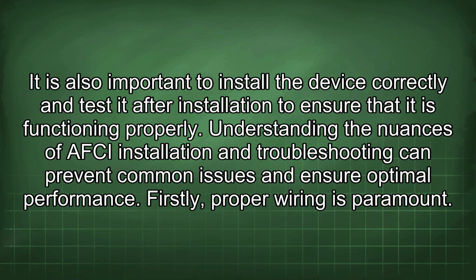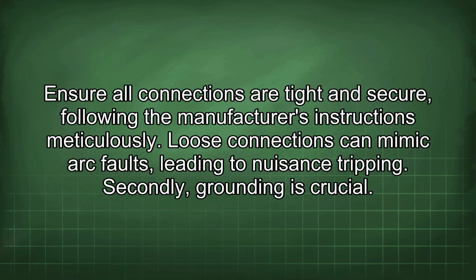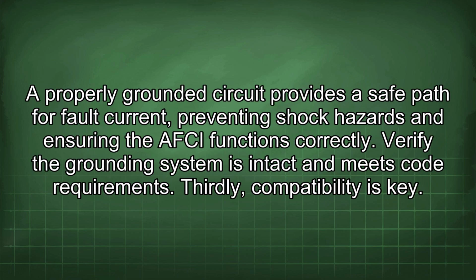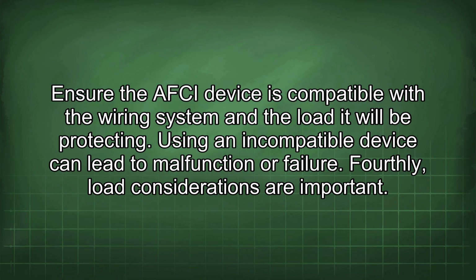Firstly, proper wiring is paramount. Ensure all connections are tight and secure, following the manufacturer's instructions meticulously. Loose connections can mimic arc faults, leading to nuisance tripping. Secondly, grounding is crucial. A properly grounded circuit provides a safe path for fault current, preventing shock hazards and ensuring the AFCI functions correctly. Verify the grounding system is intact and meets code requirements. Thirdly, compatibility is key. Ensure the AFCI device is compatible with the wiring system and the load it will be protecting. Using an incompatible device can lead to malfunction or failure.